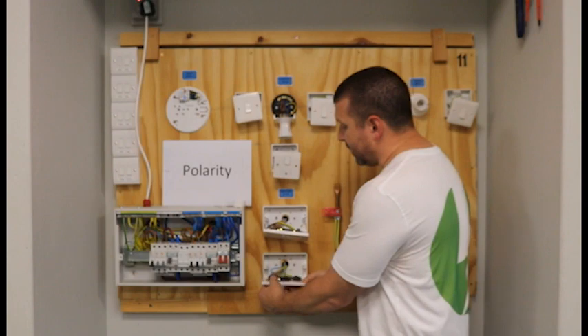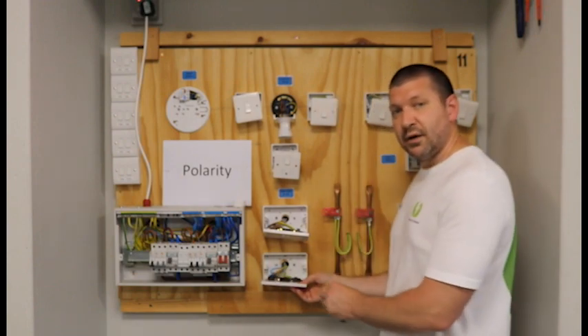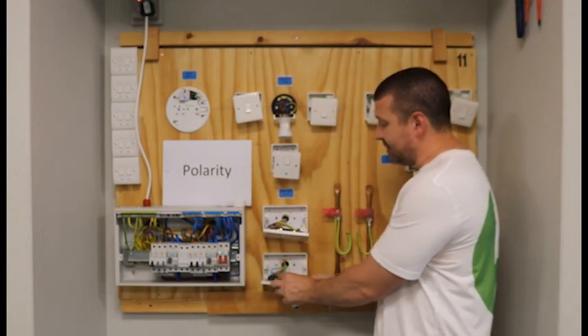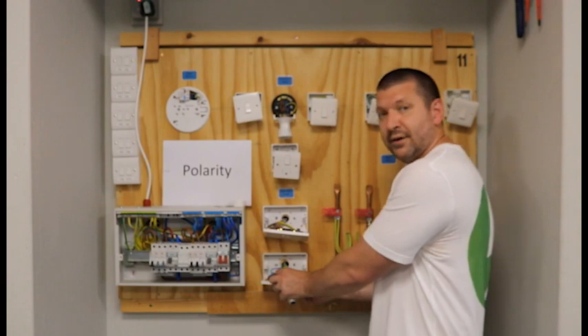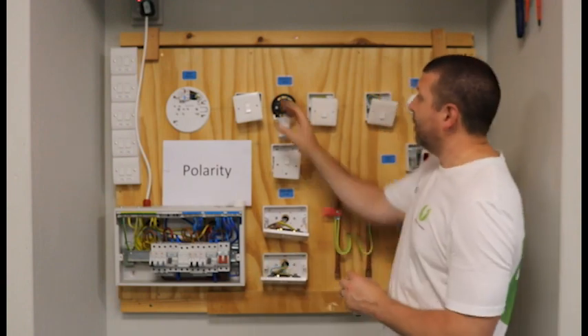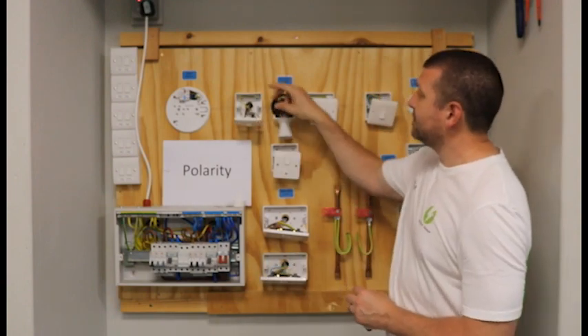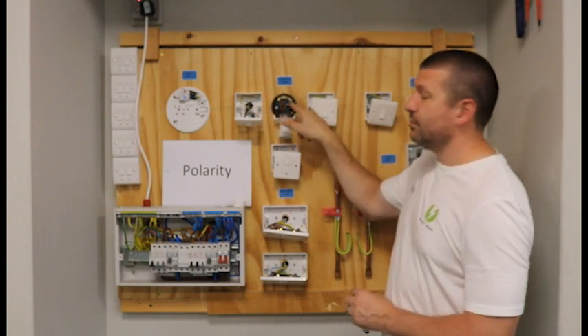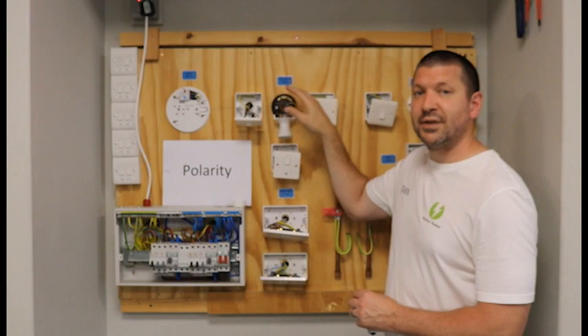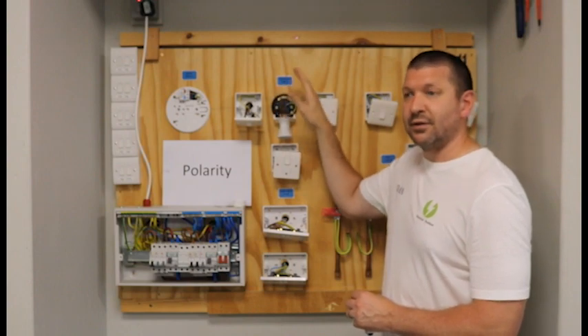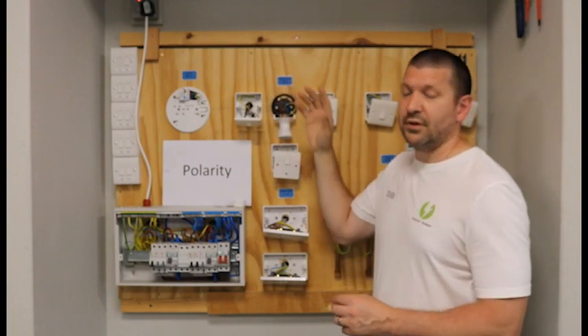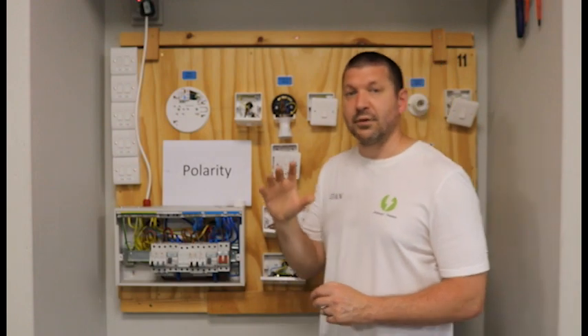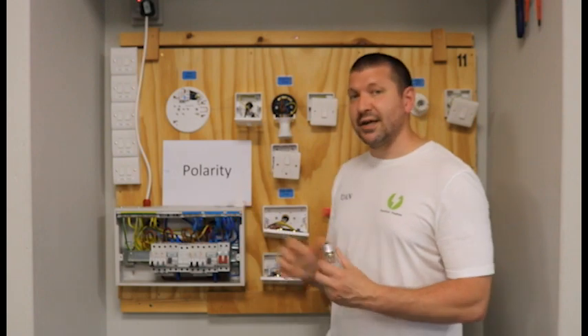So when I've gone around and done my R1 plus R2 test, I'm testing at the sockets, I'm testing between live and earth, live and neutral. And when I'm visually checking that the lives are in the lives, neutrals are in the neutrals, earth are in the earth. So if you complete your R1 plus R2 test correctly, there's no further test to do for polarity.